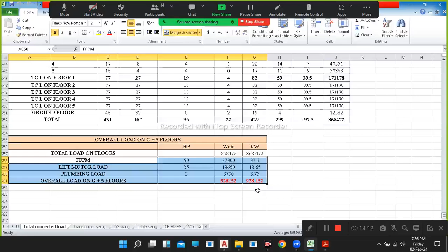So now coming to the total load, along with the lift motor, water motor, firefighting motor, he added up the total load. He got total load as 928.152 kilowatt. Now based upon this, this is the MDB load. Now based upon this MDB load, we perform the transformer calculation.